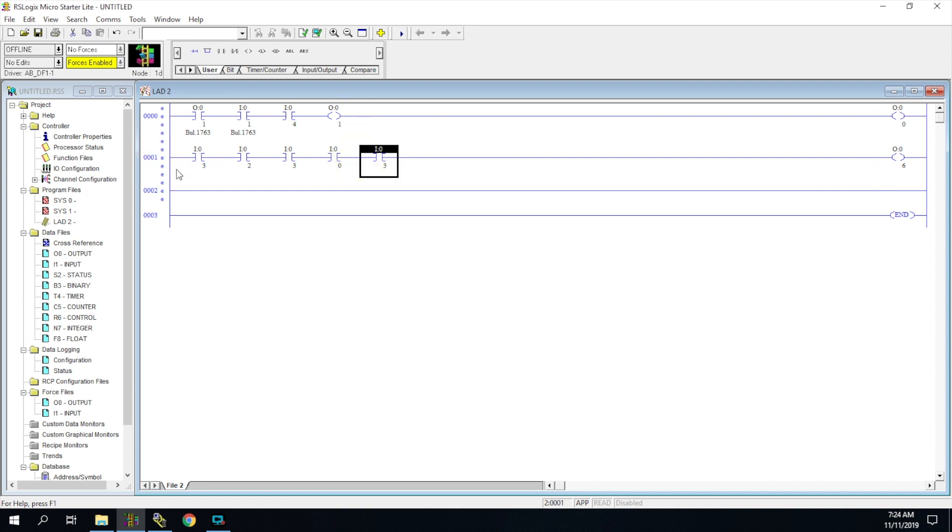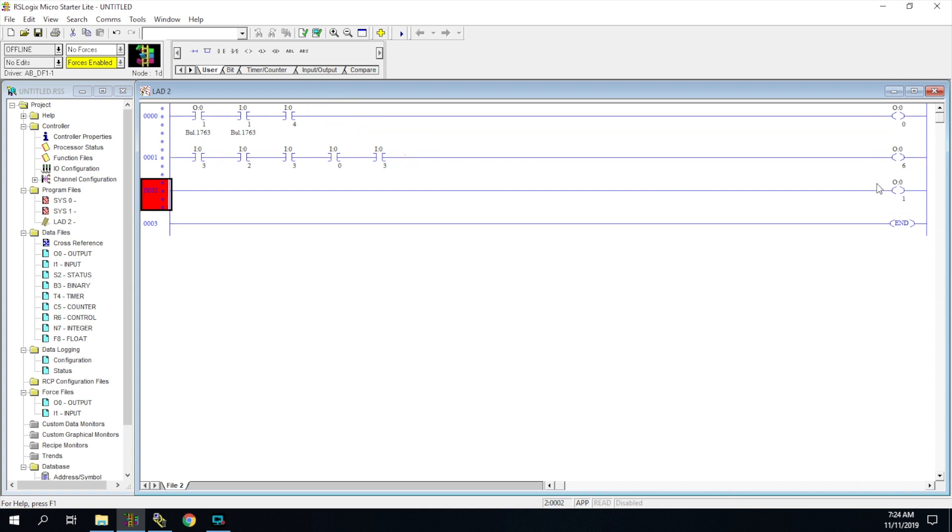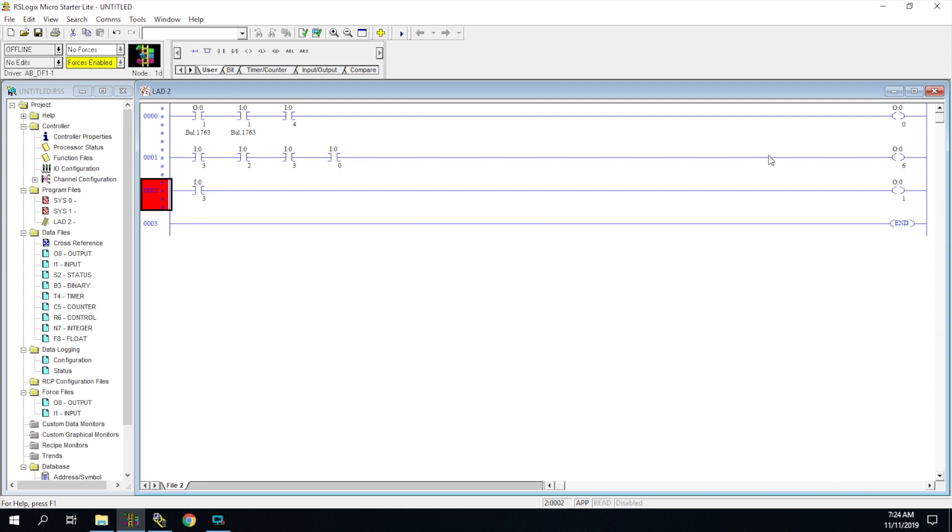Now, I want to talk a little bit more about if we have two rungs. So, if we had two rungs like this, let's say we wanted to turn both these on. In the case of a reversing motor control, one output over here would be the forward and one would be the reverse. Well, we wouldn't want the forward to come on when the reverse was on, right?